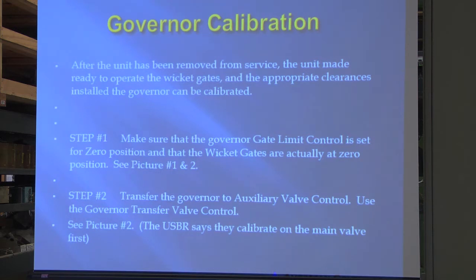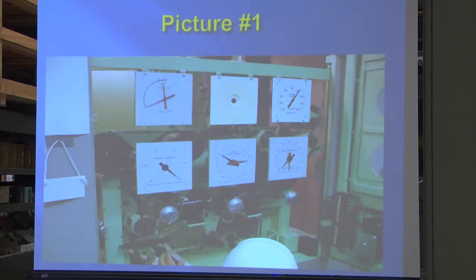The gate limit control is set for 0 position. Yeah, I didn't think it said it, speed adjust. Because that part really, until you set the actual speed of the unit at zero droop. Now have you guys seen any change on your Peltons if you set it with the droop at 5 or the droop at 0?